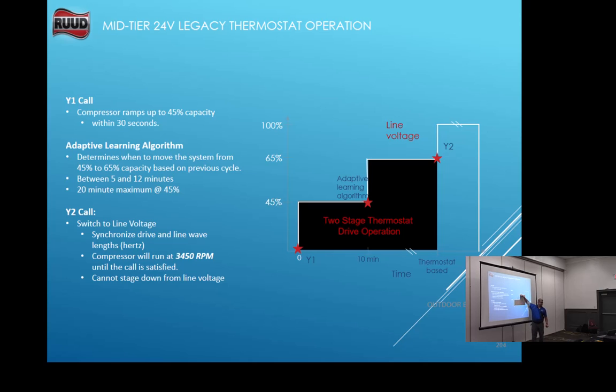Running at that one speed, 3450 RPM, I think. Then, after it sits there and runs between 5 and 12 minutes, 20 minutes max at 45%, if the temperature is not reached, it goes from line voltage again onto the contactor and goes up to 100%, second stage, or third speed. So it's really just a 2-stage compressor is the way I look at it, almost. A variable 2-stage compressor. First stage is variable, second stage isn't. Kind of the way I look at it.